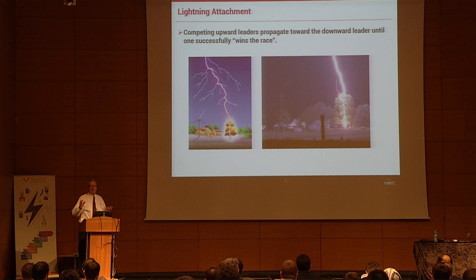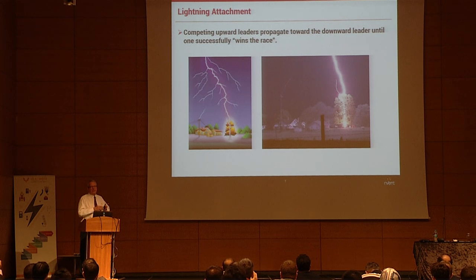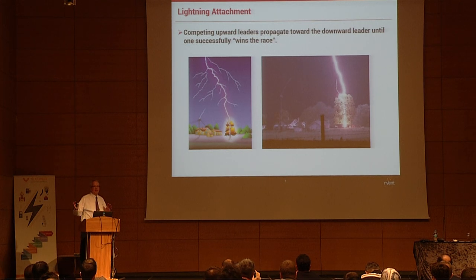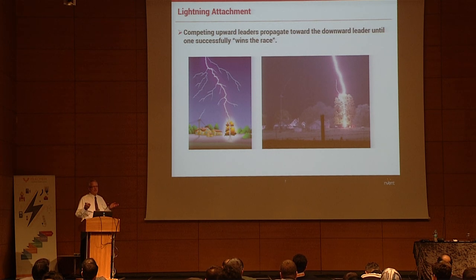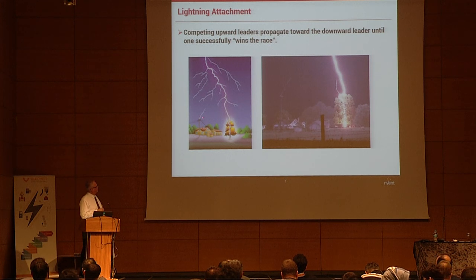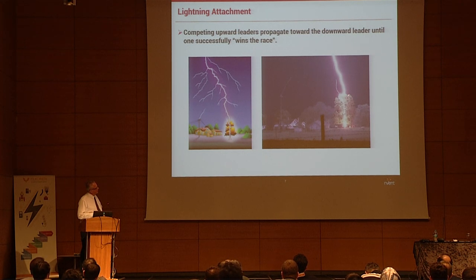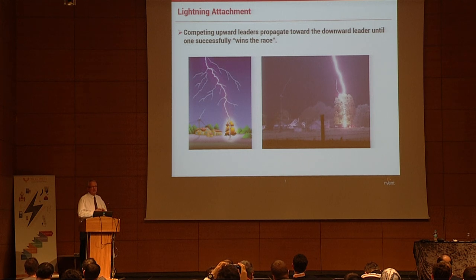Lightning is an unpredictable event of nature, and it's really difficult to judge where lightning is actually going to strike. You can never get 100% protection — at protection level one you have a 99% probability of catching the energy, but there are still some bypasses. In this case you have a power line that launched an upward leader and a tree that also launched one, but the preferred connecting point was with the tree, not the transmission line.